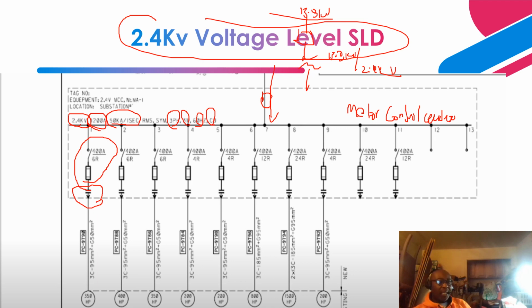Okay, so now let's talk about the disconnector switch. The rating of the disconnector switch is 400 amps, and the fuse rating is 6R. That is the rating for the fuse based on the horsepower and the full load current, so that's how the fuses are selected. Then this is the contactor, right? In motor control centers, they utilize contactors instead of breakers, because contactors can withstand many openings and closings, the energization of the motor, compared to breakers.